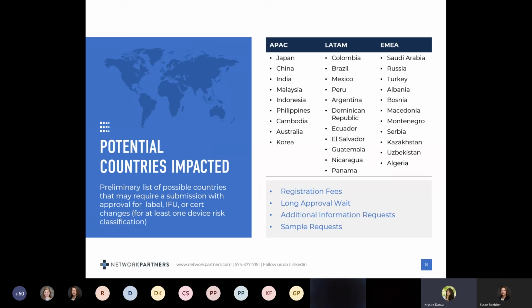Lastly, keep in mind that the health ministries who leverage CE marking are aware of the current delay and difficulties with MDR, so they may have created a guidance specifically addressing it. TGA, for example, has put out an MDR implications for Australia guidance. Like Australia, countries may be preparing alternative pathways, amendments, or overseas regulatory agreements if there are delays in obtaining or maintaining your European conformity assessment evidence. So make sure your regulatory intelligence is staying up to date with the global agency initiatives related to MDR.